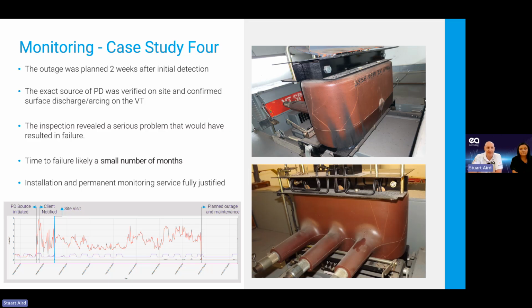The PD type sound increased. Our algorithm can tell us that we think it sounds like partial discharge as well with the monitoring system. So at that point, we can then speak to the local staff and ask them to go down to the substation and carry out an investigation. So at this point, we've picked it up on the very first day, and it's been running for about 2 weeks. And they can plan their outage, they can plan what the next steps are on this.